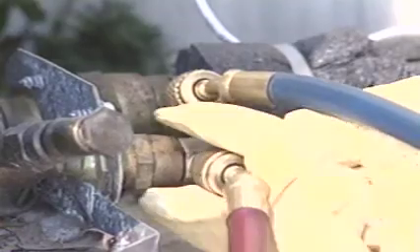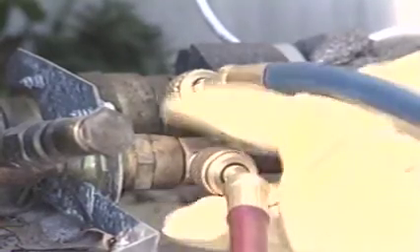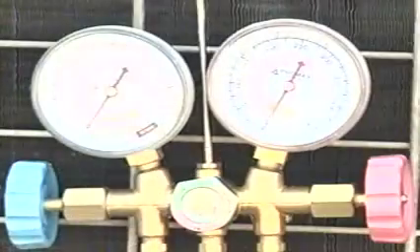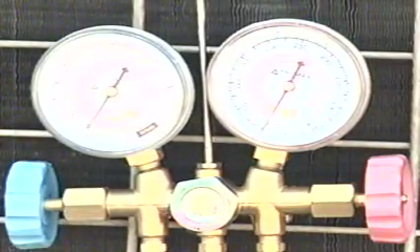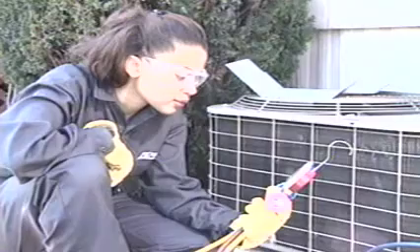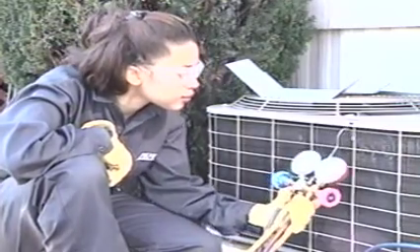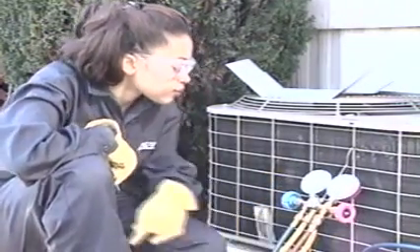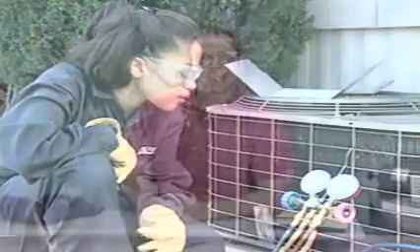Why? Well, either the switch is defective or the switch is good, but pressure in the sealed system is low. Check the pressure first by attaching manifold gauges to the sealed system. Both the high side and low side gauges show 0 psig. This shows that the low pressure switch is probably okay, and the problem is that the system has lost its charge. A 0 psig reading on a sealed system is major enough that you can usually see the leak, and sometimes even hear it. But in this case, there's no obvious leak.